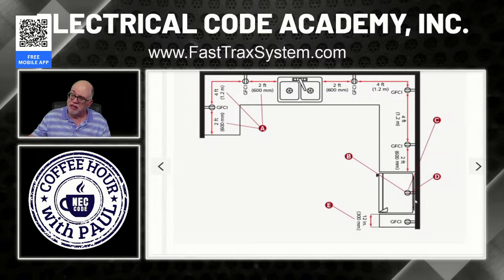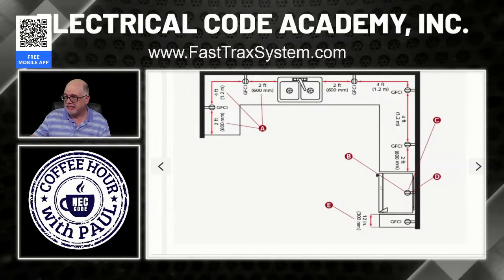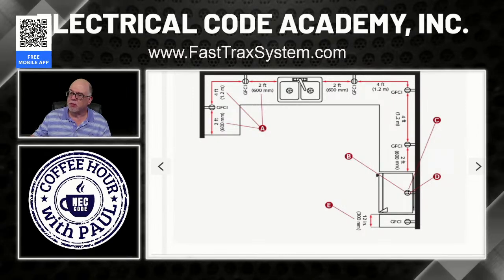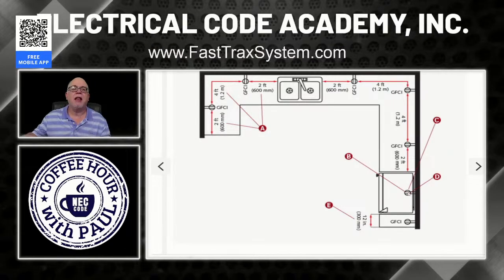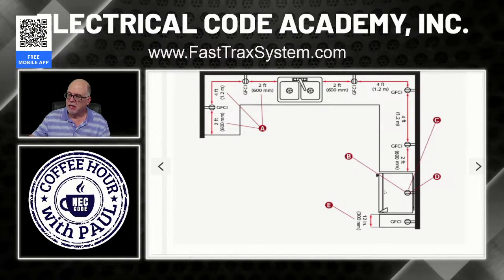Also, since it does not serve a countertop, it would not be required to be GFCI protected. Unless, of course, if you're familiar with 210.8, this receptacle happened to be within 6 feet of a sink, then it would be required to be what? GFCI protected. In this case, it's a long way from the sink, so it would not be GFCI protected, okay?